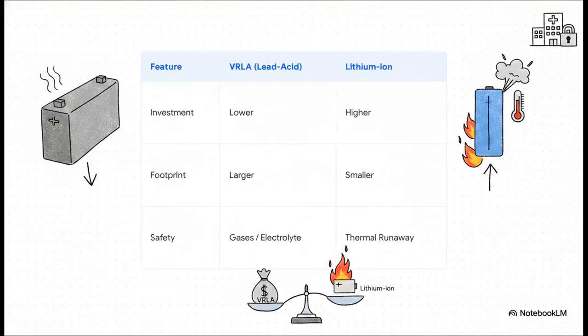When the grid actually fails, this is your ultimate lifeline. When choosing your battery chemistry, you're usually weighing traditional VRLA, standard lead acid, against lithium-ion. You have to balance the lower initial cost of lead acid against the much smaller, lighter footprint of lithium. But honestly, the biggest deciding factor must be fire safety constraints. Lithium is incredibly popular right now, but it carries specific thermal runaway risks. You can't just pick it for its lifespan. You have to ensure your building's specific fire suppression systems and local fire codes actually allow it.